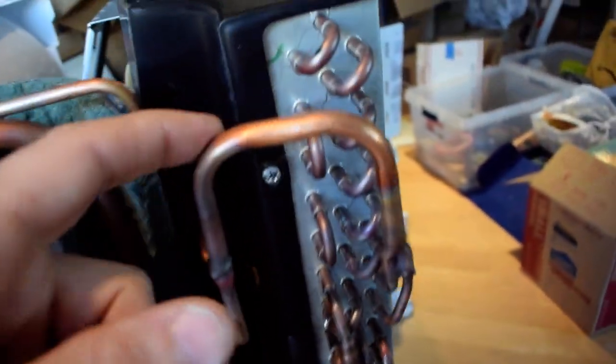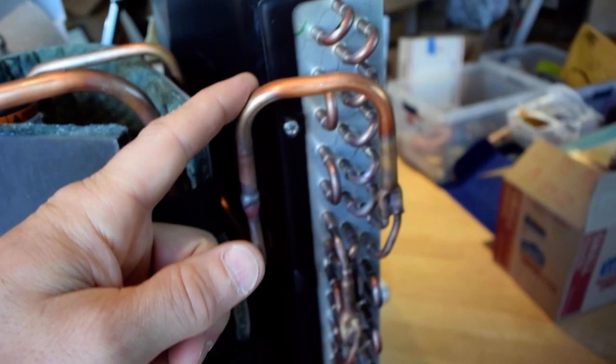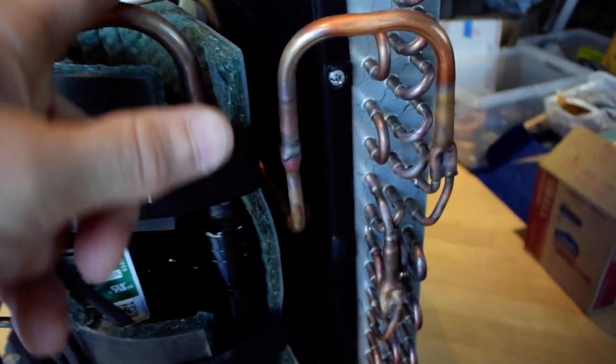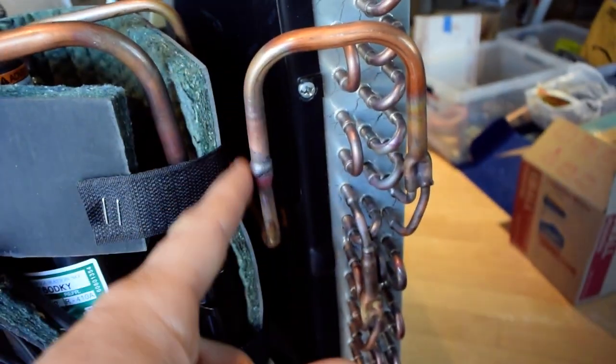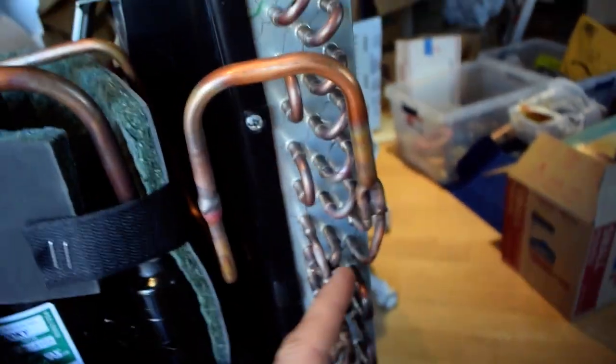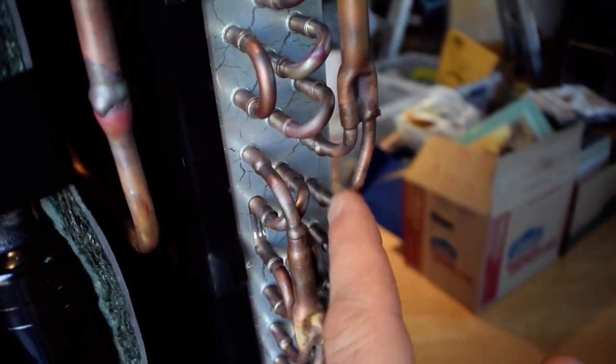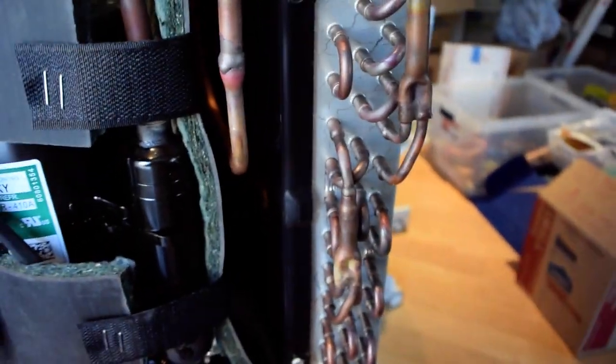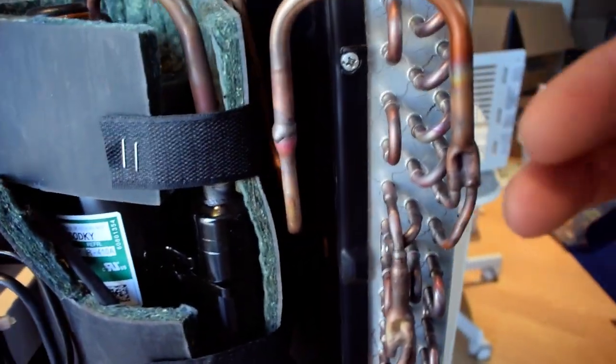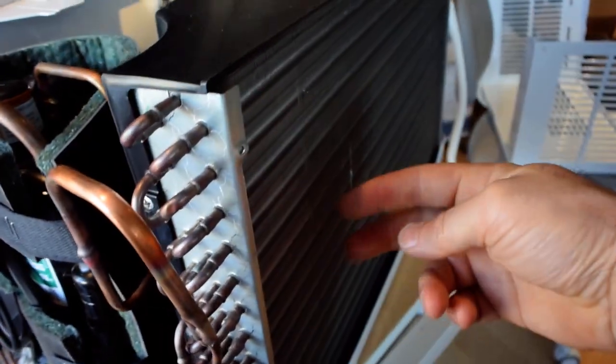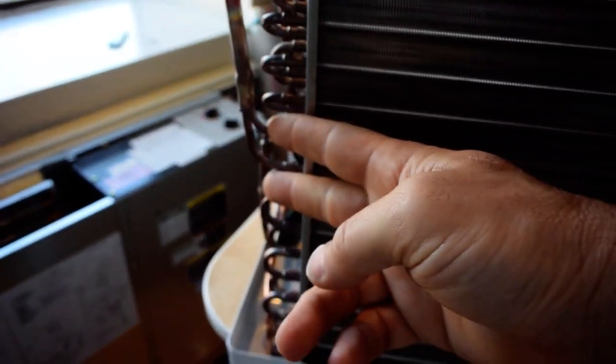Up here an interesting thing happens. This is the hot gas line coming out of the compressor. It gets split here and makes two different trips across the condenser coil. So those two circuits start here, go like this and then they split up.